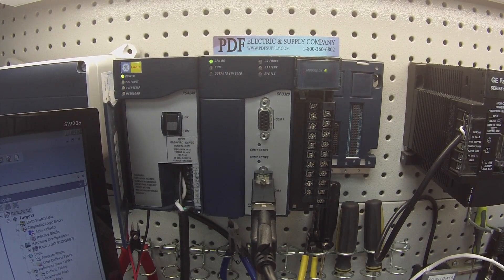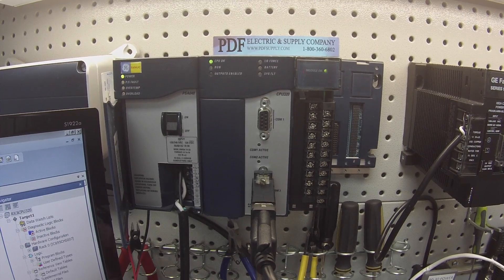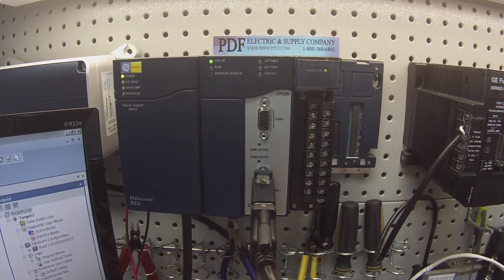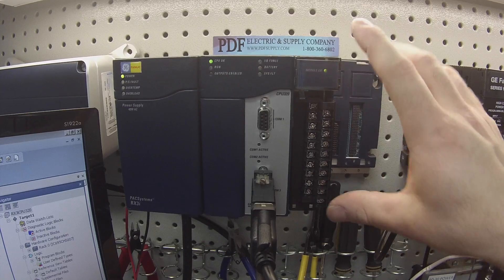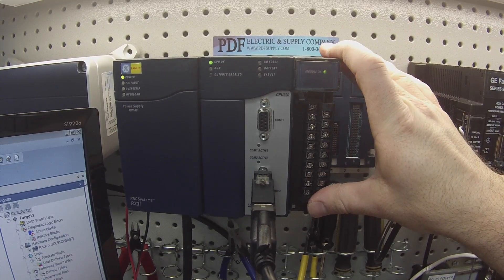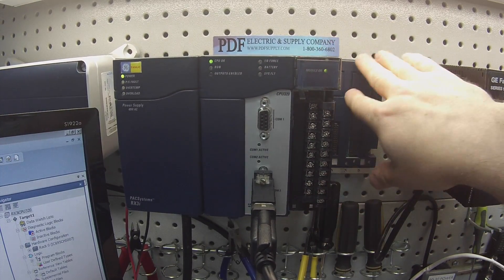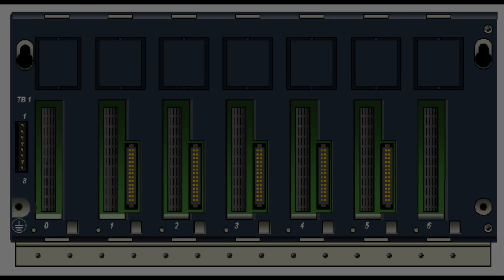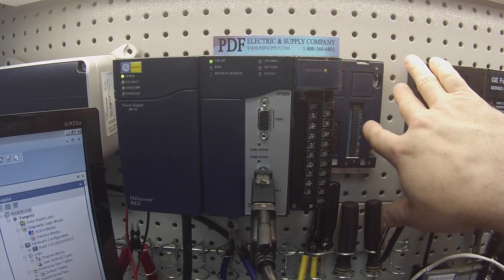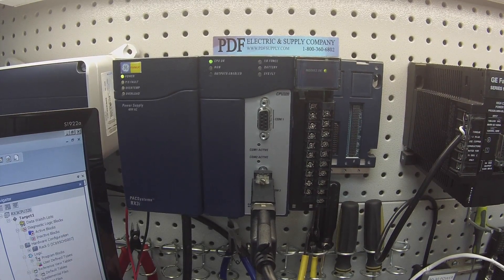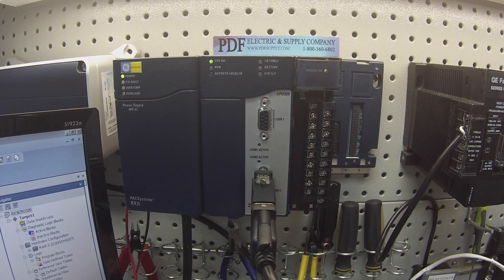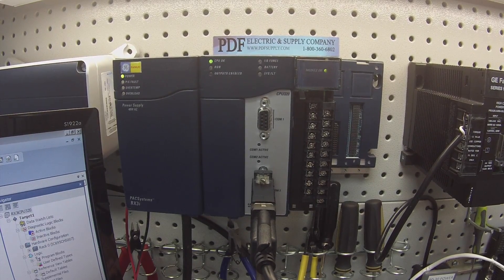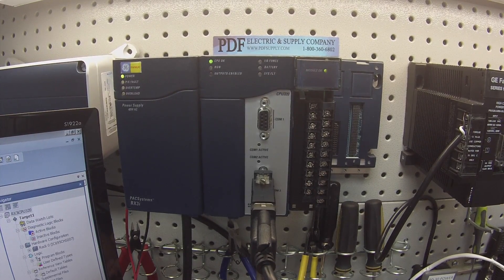Before I get started, I want to let you guys know that in order to get this module OK light on and power up this particular module on the rack that I'm using, which is an IC695CHS007 slot rack and also any of the other main racks that you would be using for this type of test, it has a power input. It needs a 24 volt DC power input on the rack itself.